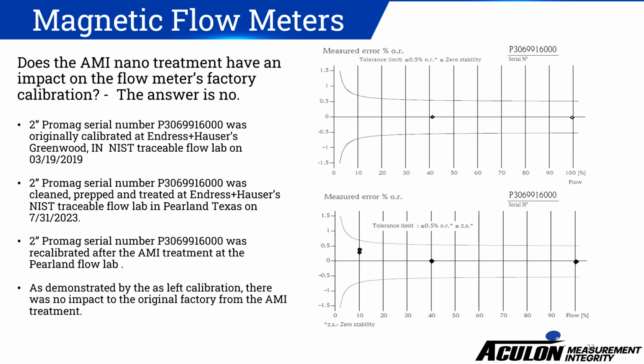What you're looking at here are two graphs. The upper graph is the original flow calibration from the factory, which is NIST traceable. This original calibration was done March 19th, 2019. In July of 2023, we took that meter and cleaned, prepped, and treated it at a facility which also has a NIST traceable flow lab. After the meter was cleaned, prepped, and treated, the meter was recalibrated, and as you can see on the lower graph, the calibration points did not move. So as demonstrated by the as found and as left calibration, there was no impact to the factory calibration from the AMI process.